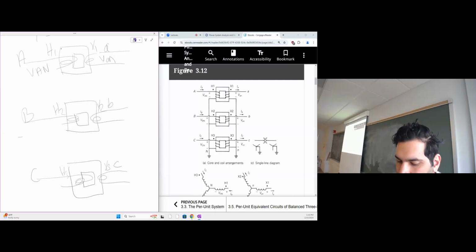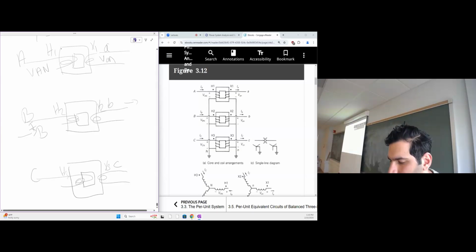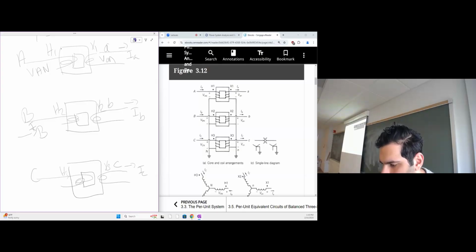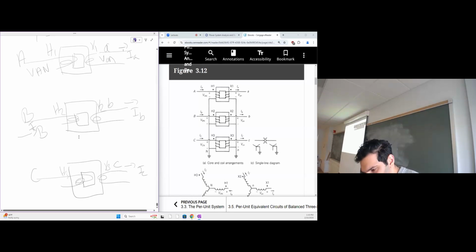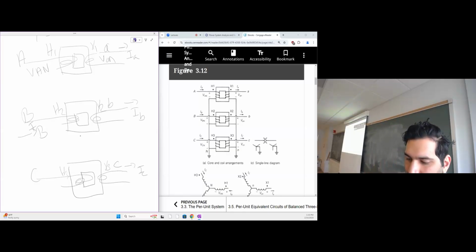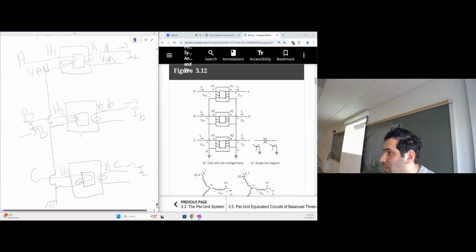And we also apply like IB from here. We get from here IB small, and from here IC small. Here IA small, okay? So this is an easy structure here. It looks to be star to star, and we have a grounding connection. So here I just have 3 single-phase transformers, ungrounded, and I don't see right now if they are star or delta connection. This is my next step. So to make a ground connection, I need to make sure that they are all connected. This means that there's no connection here. They are commonly connected to a ground. Here's the neutral.